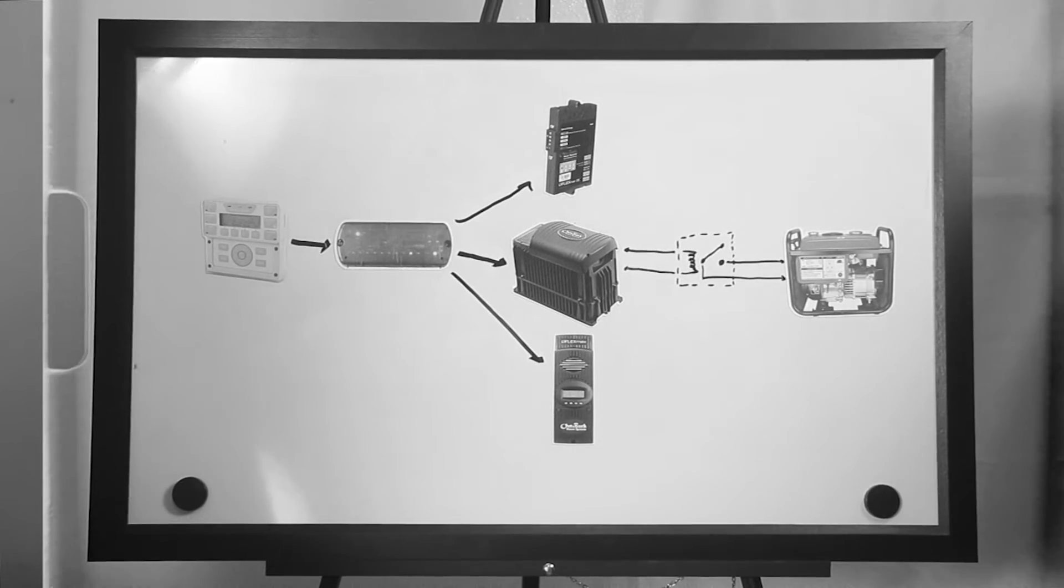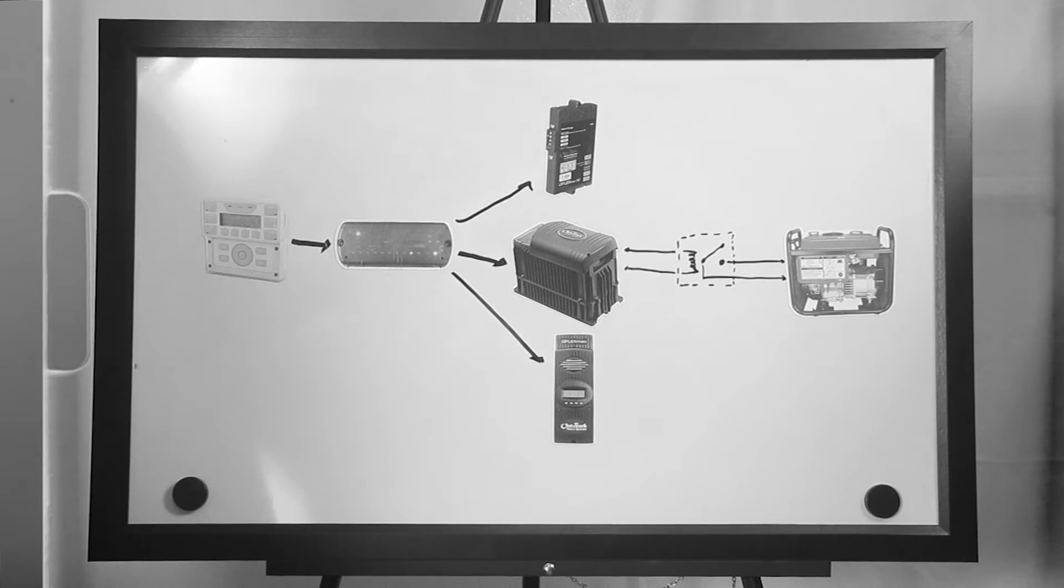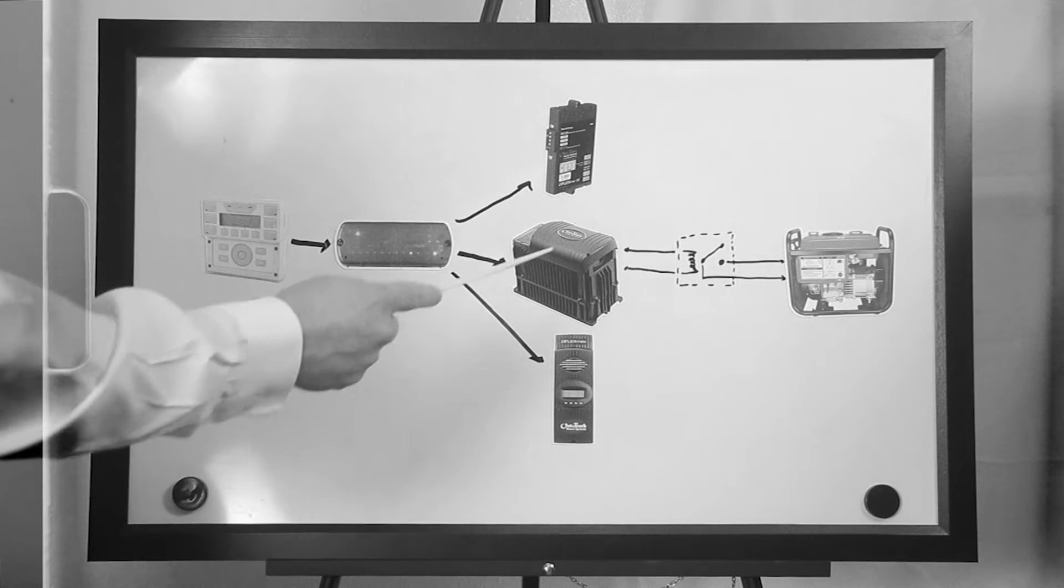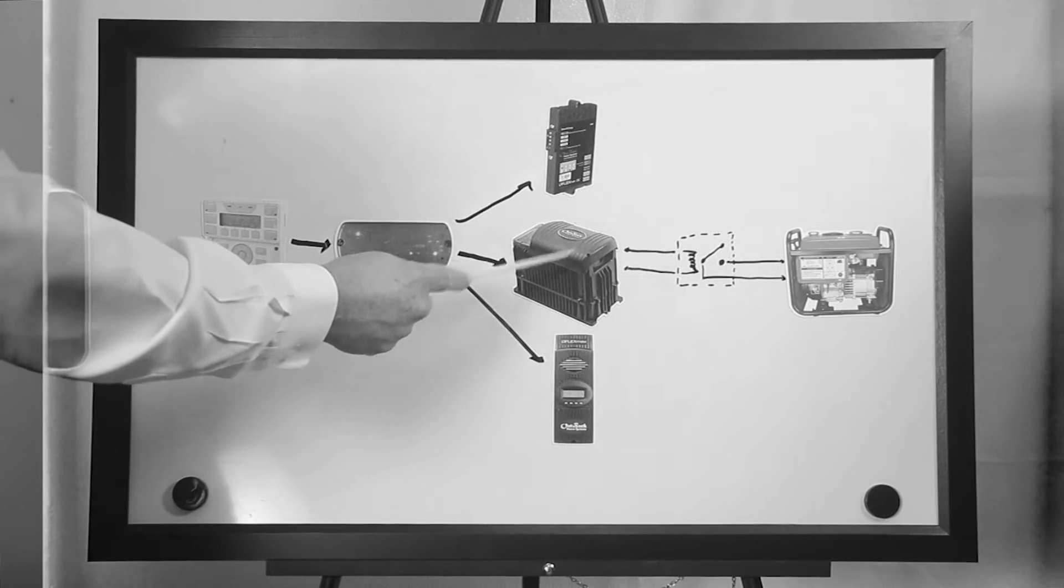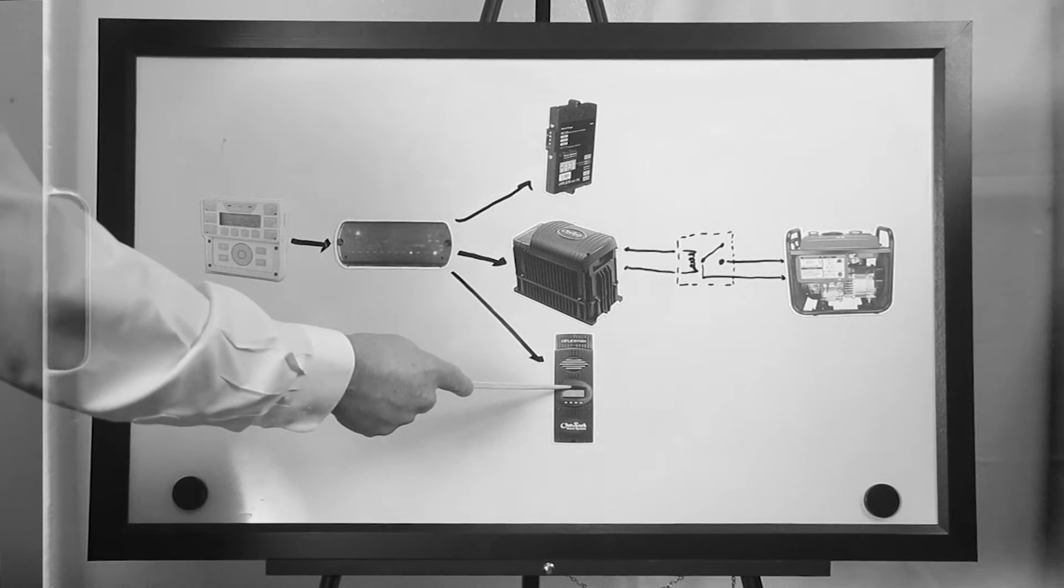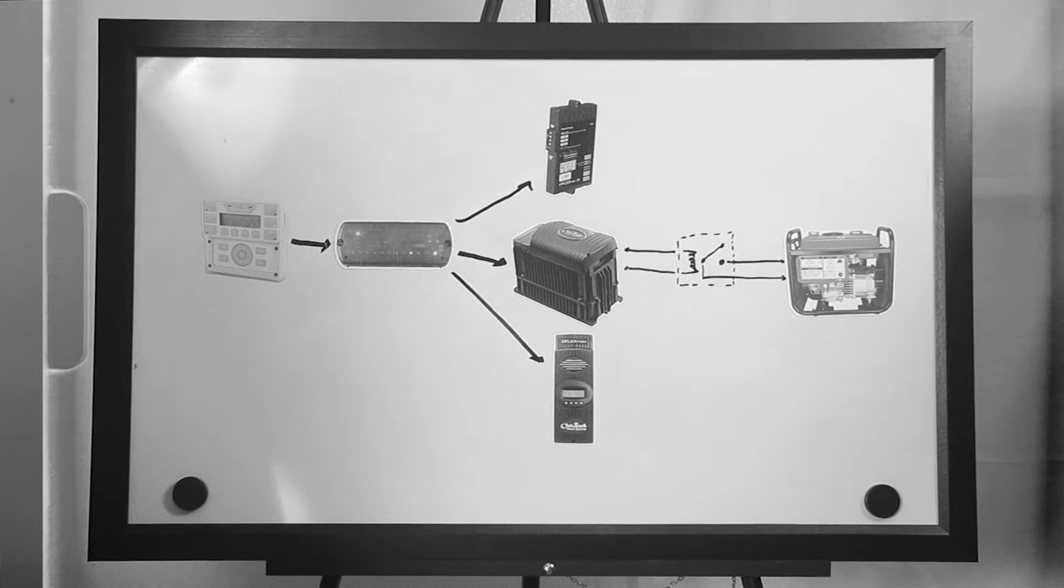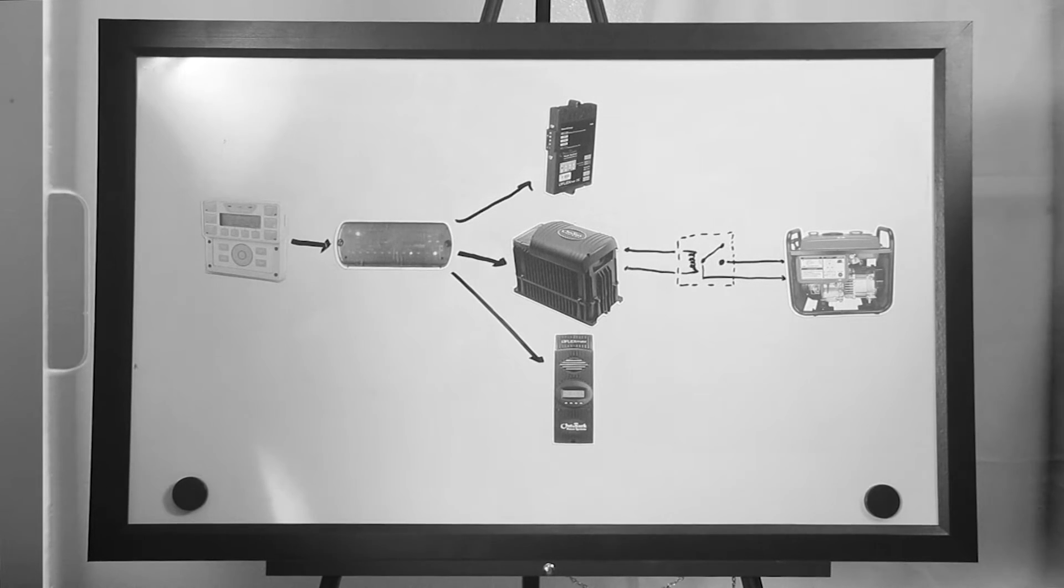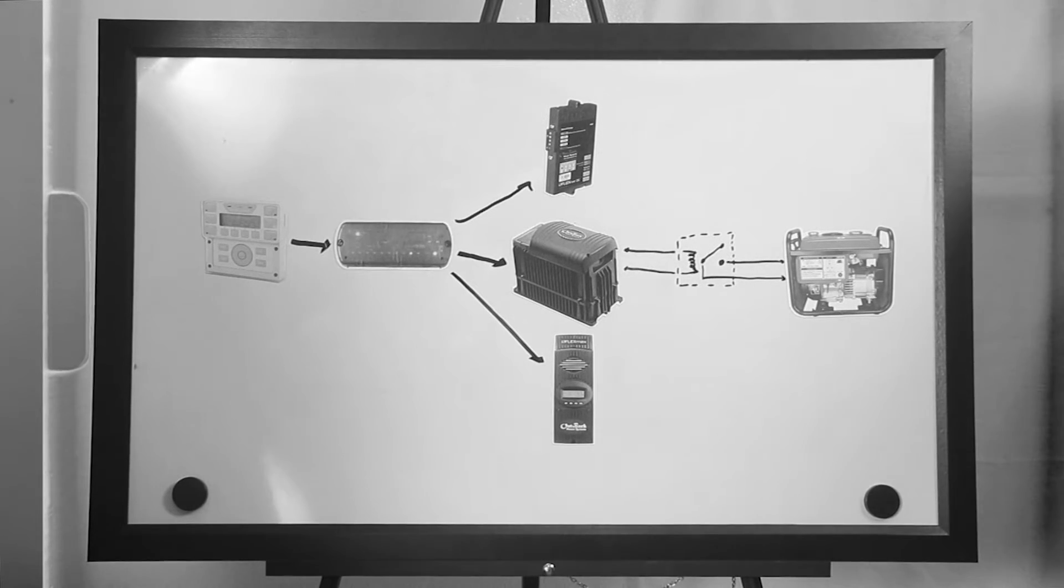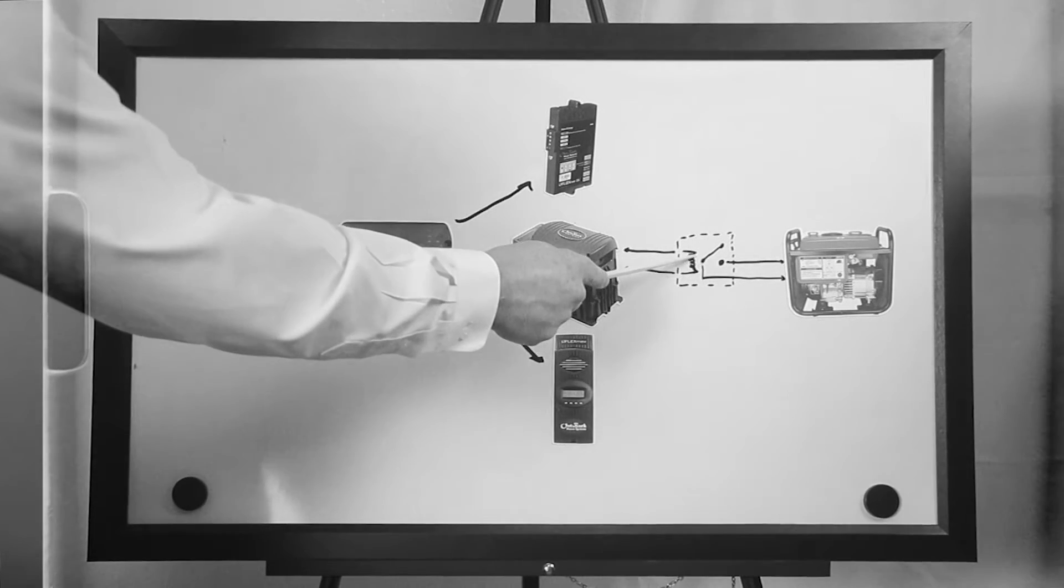Once one of these start conditions are met, AGS will utilize the auxiliary output of an Outback device, such as the FX inverter or a charge controller, to create a voltage signal that can then power a normally opened relay. The relay gets wired to the generator two-wire start circuit.